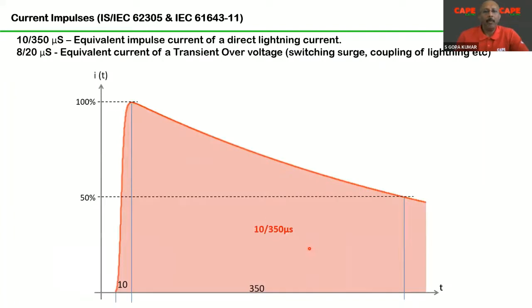When you look at lightning protection, people always ask, what is this 10 by 350 microseconds? The energy content of lightning has been generated in a laboratory as a wave shape. Finally, whatever components we are using need to be tested. For that testing, we need a standardized energy form so that all manufacturers are at the same level to do the test.